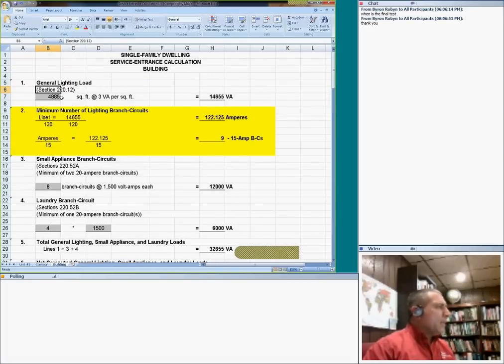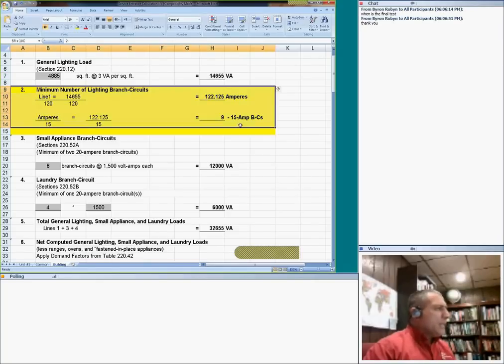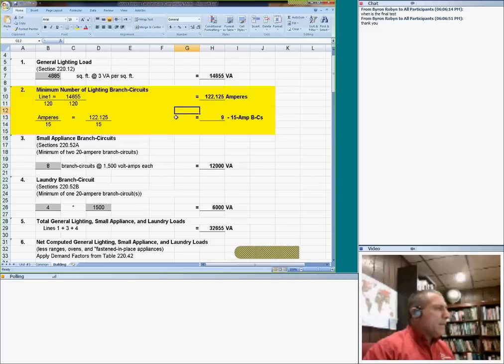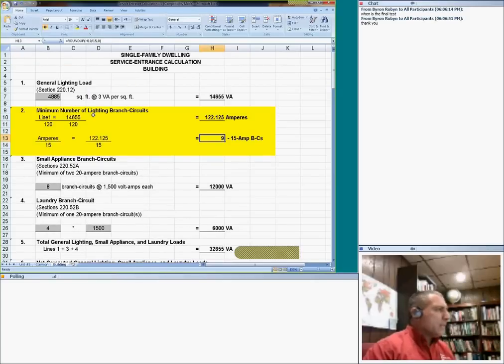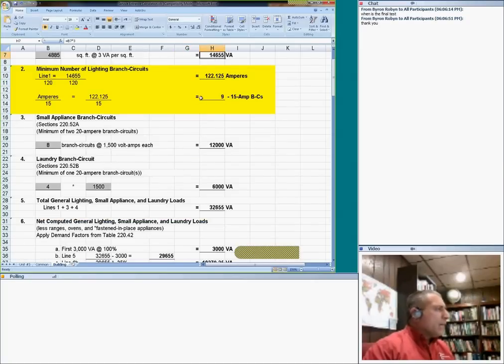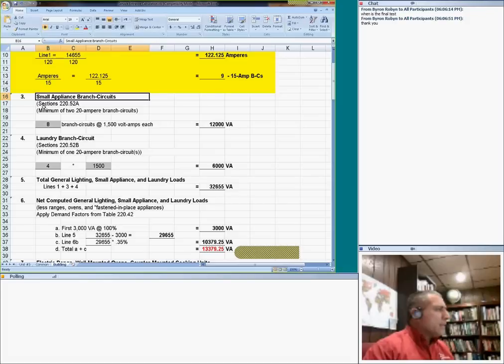Single family dwelling unit. The square footage of the building, my building is almost 5,000 square feet. Multiply by 3, that gets you this amount, 14,000. Ignore this, this is just how many 15 amp circuits you need. You basically take this, divide by 120, get this amount, and divide by 15, get you 9 circuits. So 9 15 amp circuits to feed the lighting and small appliance circuits, based on the code. But this is the volt-amps for general lighting. The next step, guys, is for the two small appliance circuits.